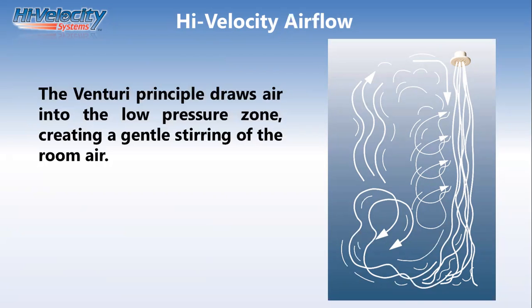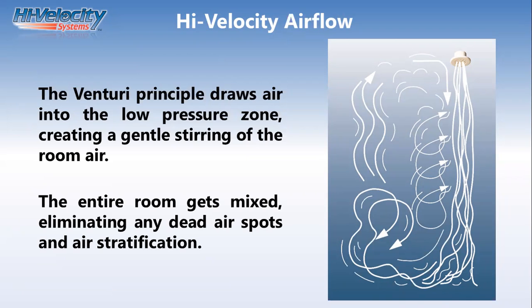Because of how we're mixing and moving air, no matter where we locate our outlets, in the ceiling, in the floor, or in the wall, we are going to get a total mix of that room air, giving us even temperature from floor to ceiling throughout these structures. In a high velocity conditioned home, you can put a thermometer on the ceiling, a thermometer on the floor, and see less than a degree of difference. And this really excels in vaulted ceiling type of applications.